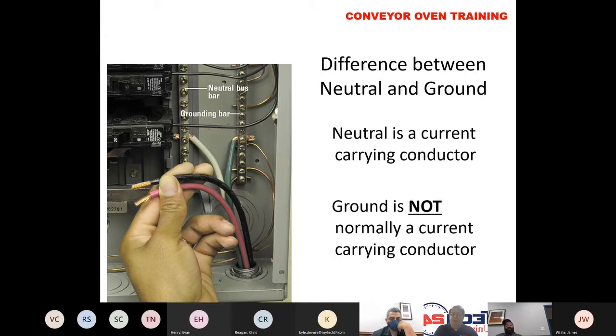There is a difference between neutral and ground. Neutral is designed to be a current carrying conductor, meaning that it's going to be energized and carrying current all the time. Ground is not normally designed to be a current carrying conductor. The only time a ground wire would carry current is when we have a short to ground, and that is only going to happen long enough for the breaker to trip, which is just a second.